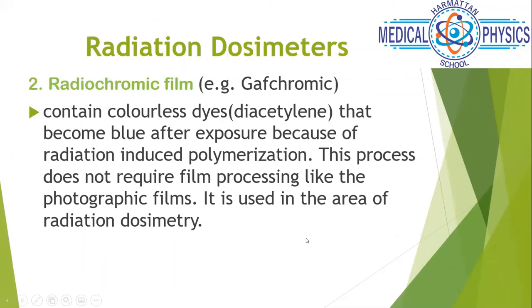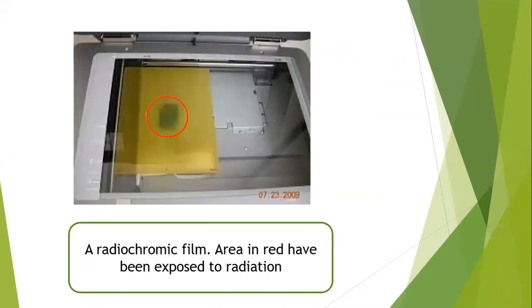The next dosimeter type is the radiochromic film — also called Gafchromic film. They contain a colorless dye that becomes blue after exposure because of radiation-induced polymerization. This process does not require film processing like other photographic films. It is used in the area of radiation dosimetry — we use them quite extensively in radiotherapy. The film appears yellowish in color and you can see the blue areas where radiation exposure has occurred. We use a scanner to process results in this case.